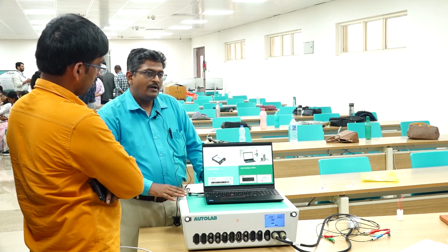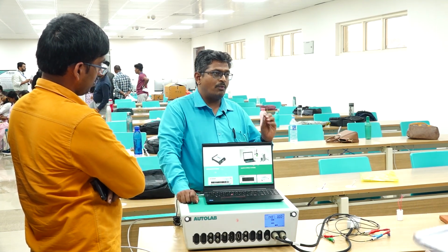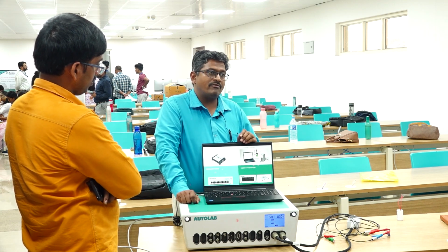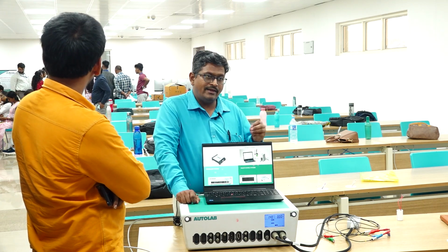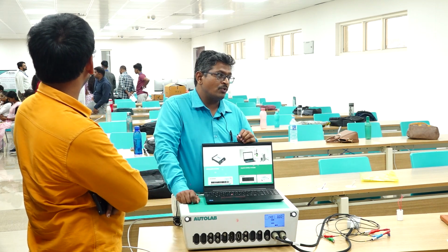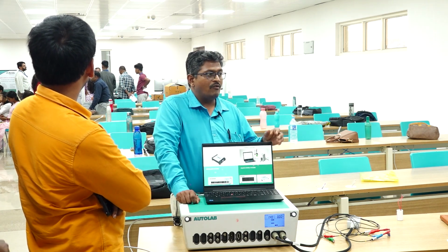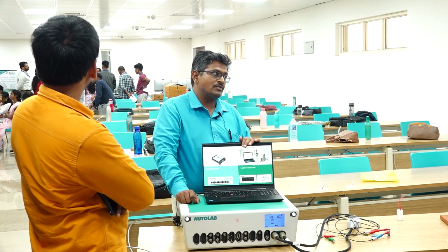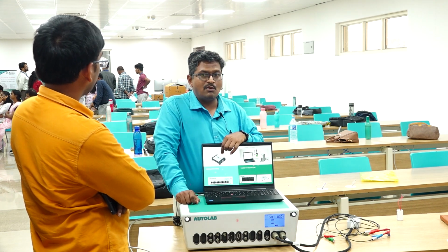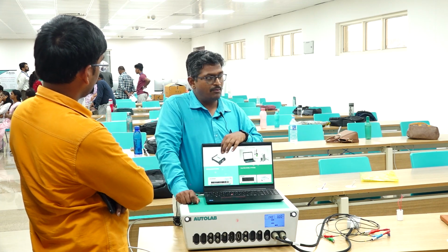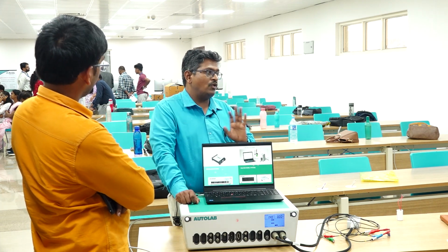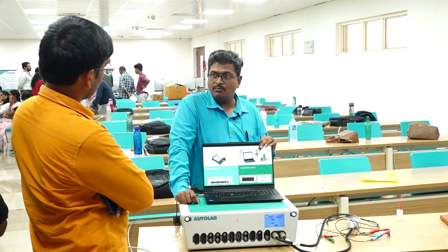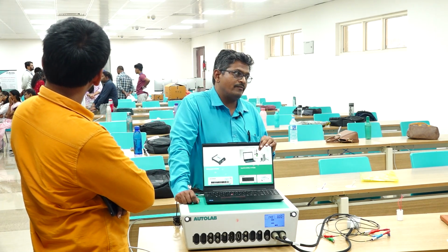A compact instrument comes with a potentiostat, galvanostat with additional modules. For example, if you want to perform an RRDE experiment, it requires a bipotentiostatic mode, which is an add-on module. The modules which are connected to the potentiostat, galvanostat are called additional modules. The simple instrument does not provide any additional modules, it is just a potentiostat, galvanostat. A compact instrument can provide additional modules, but it is limited to only one module.